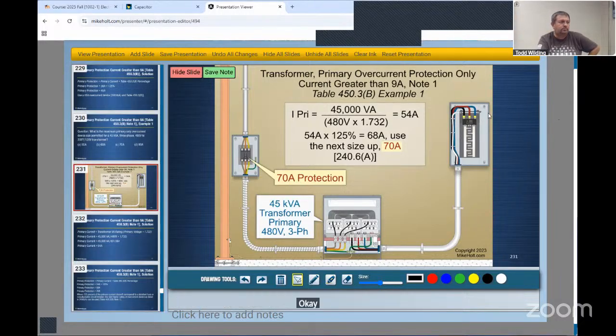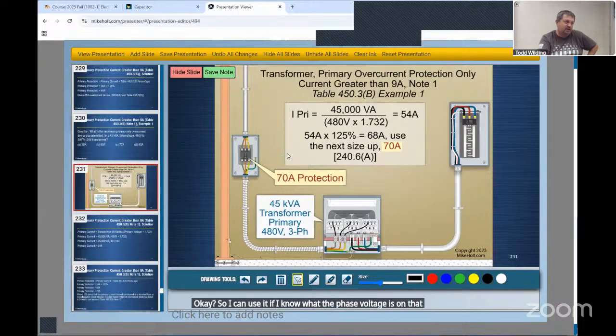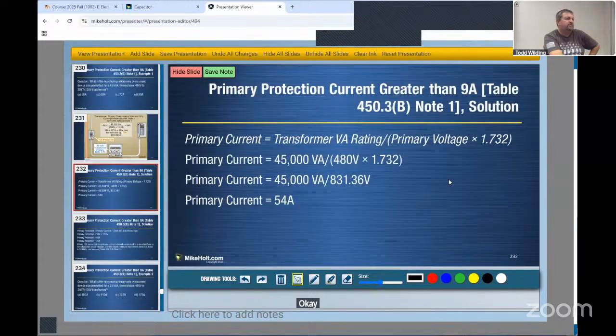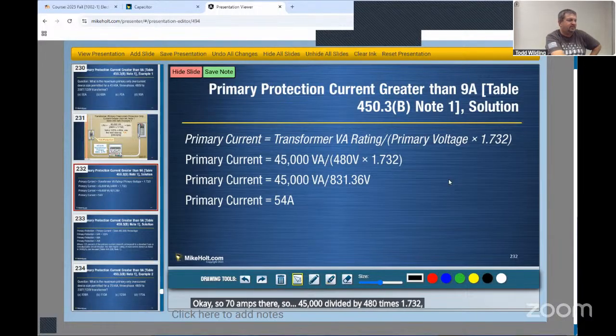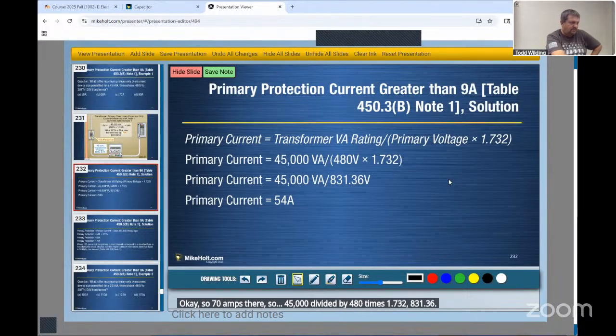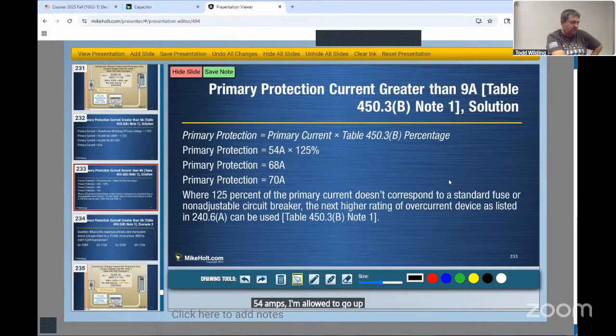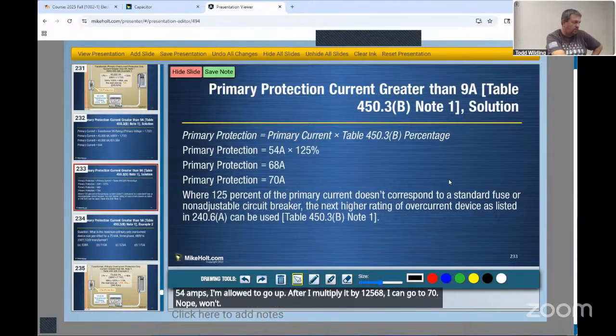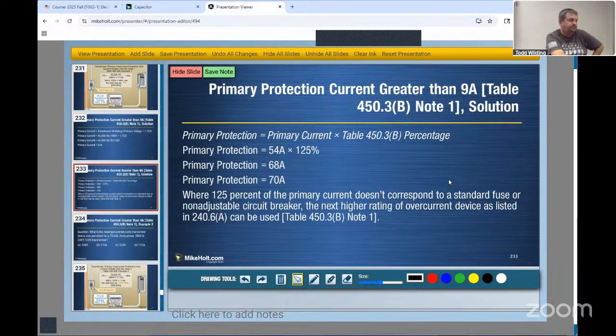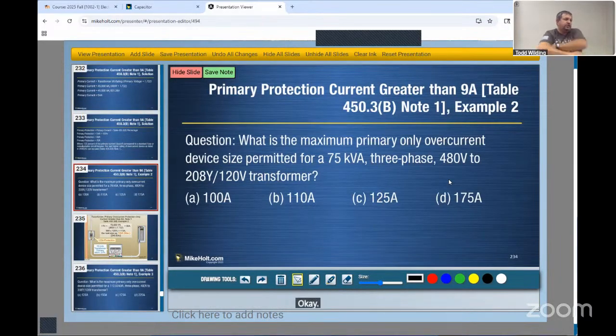Okay. So I can use it if I know what the phase voltage is on that, and I'd be willing to bet it's a Y. So 70 amps there. 45,000 divided by 480 times 1.732 is 54 amps. I am allowed to go up. After I multiply it by 125%, I can go to 70.